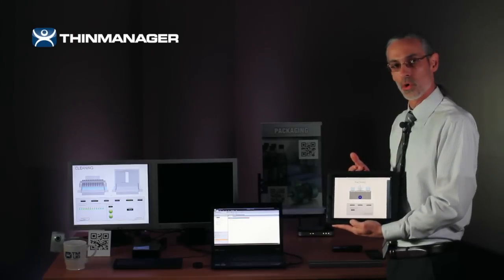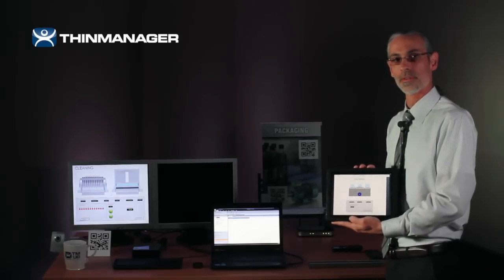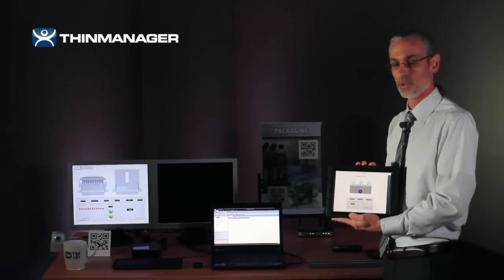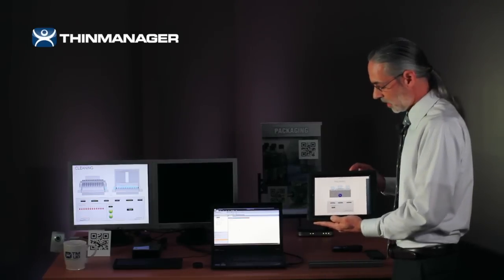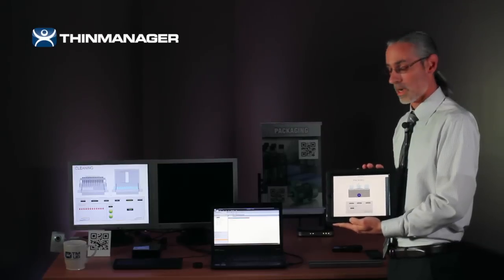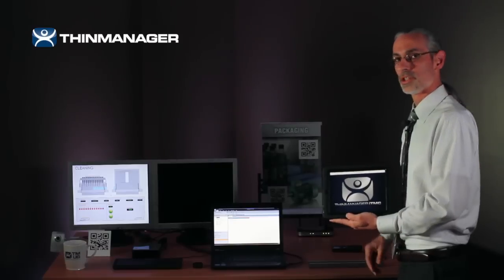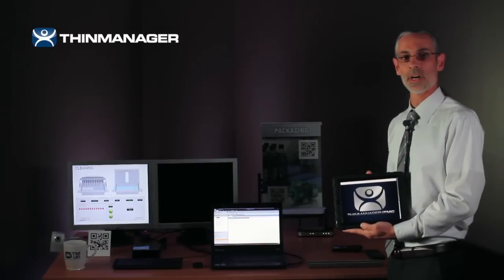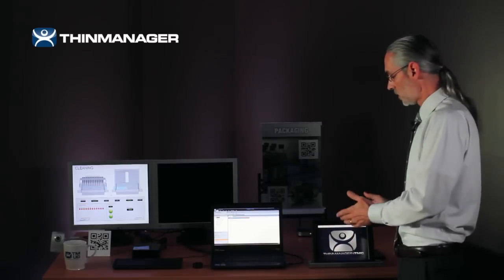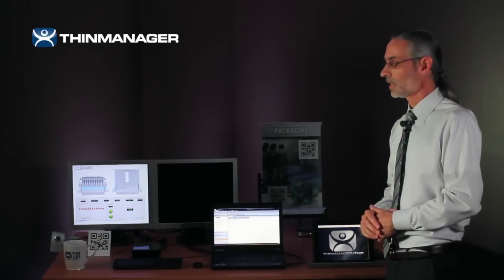What we've done is clone the application — in other words, we spun up another session within our terminal server environment, so there could be a licensing consideration since you've used another instance of the software. But this keeps you from the expense of a tethered terminal. When the operator is through, they simply leave, the application goes away, and the mobile device can be left near the conveyor system as an inexpensive way to have an HMI in an area where you don't want to drop a tethered terminal. That's cloning.